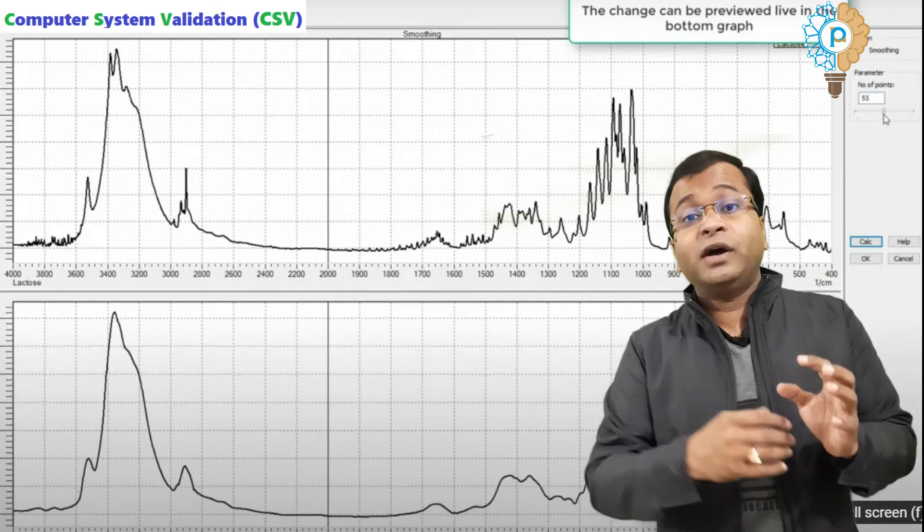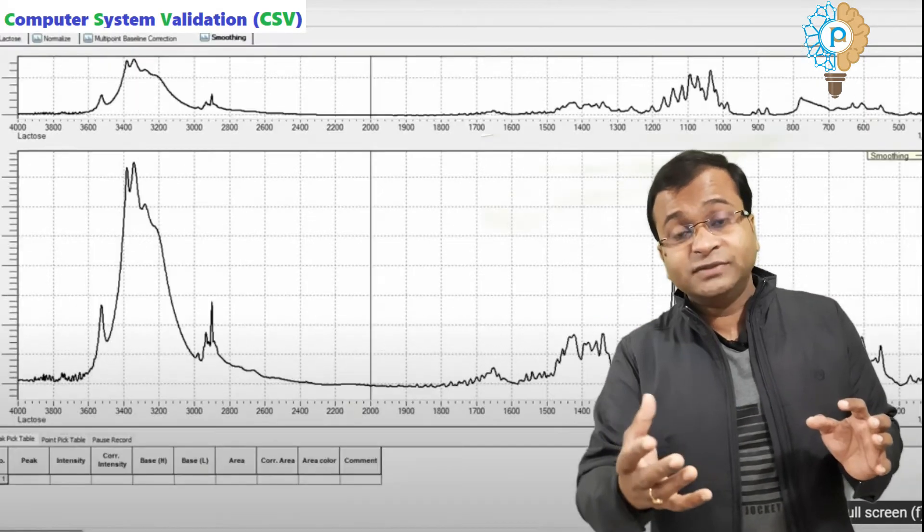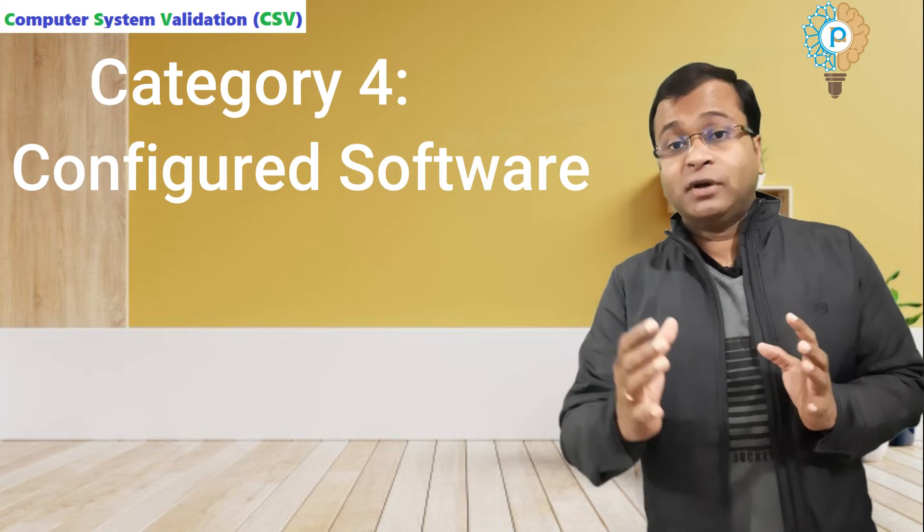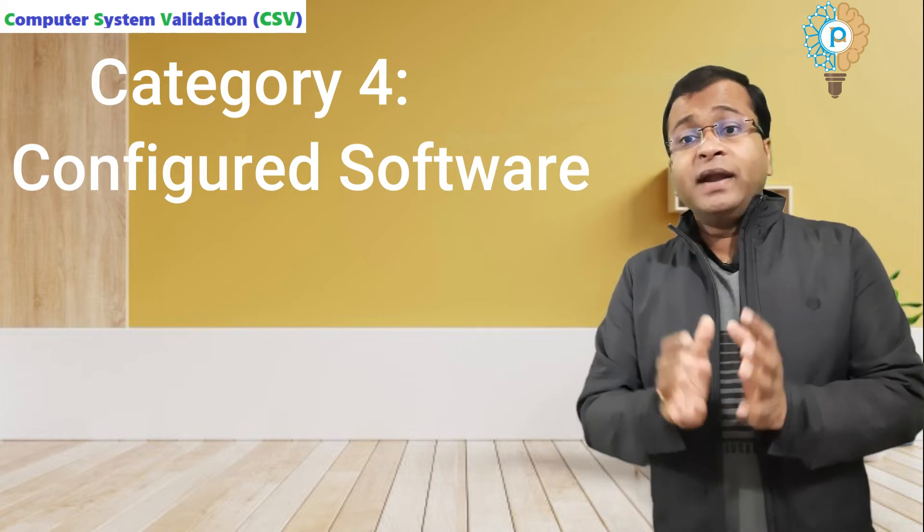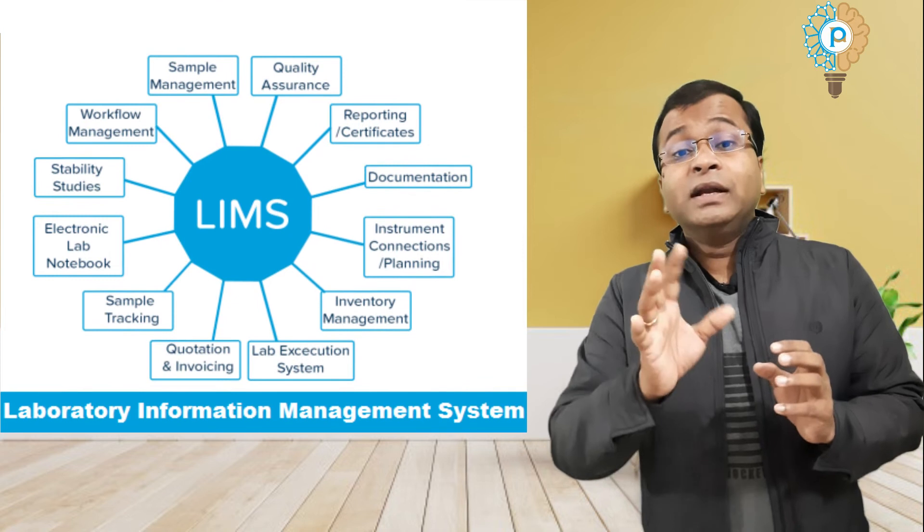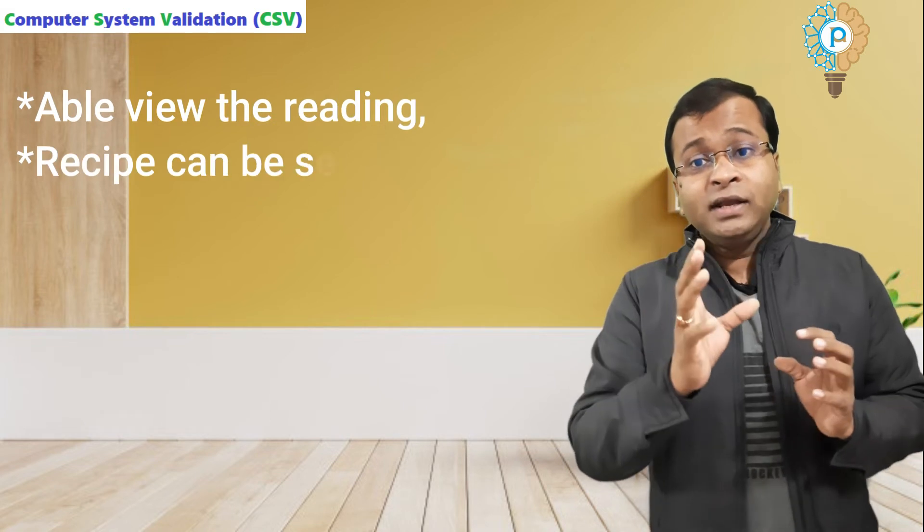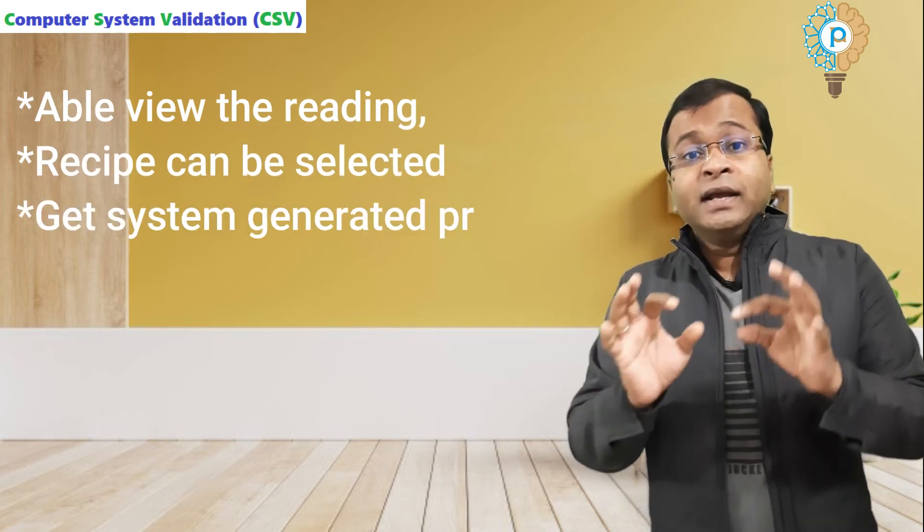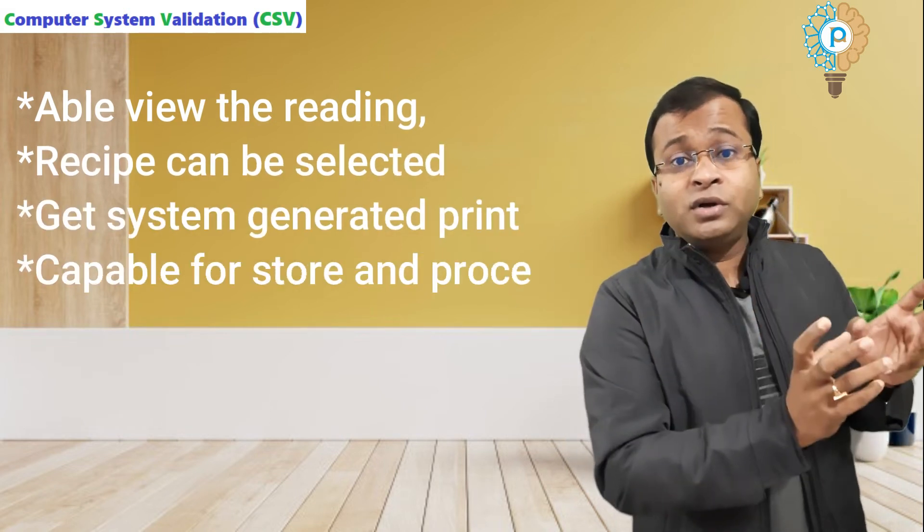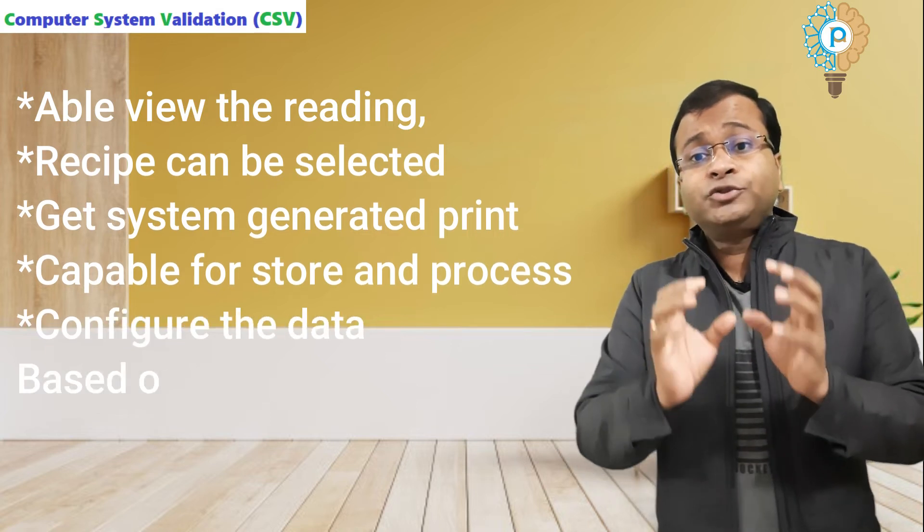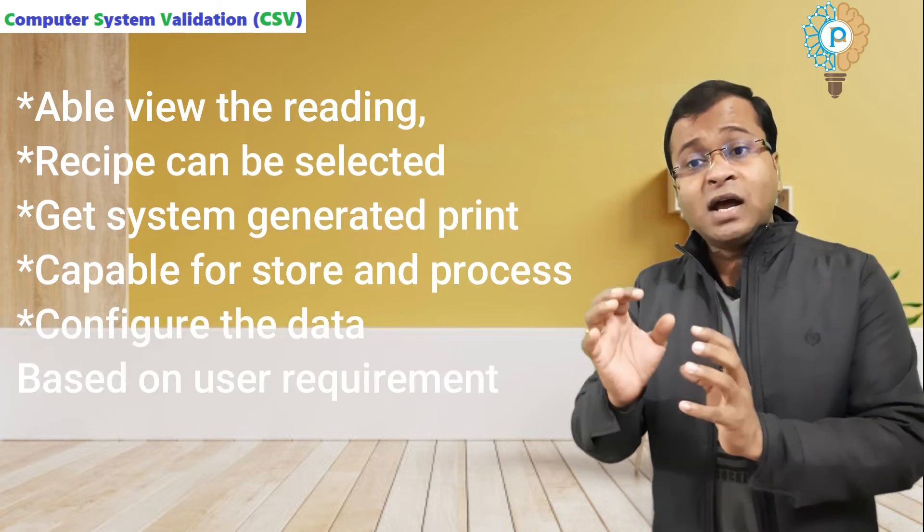Category 4 is configured software. Here, the guideline describes software applications which are configured to meet the specifications of business requirements. Examples include LIMS, SCADA, DCS, CDS, etc., where you can view the reading, recipe can be selected, get the system-generated printout, and are capable of storing and processing the data and configuring the data based on user requirements.